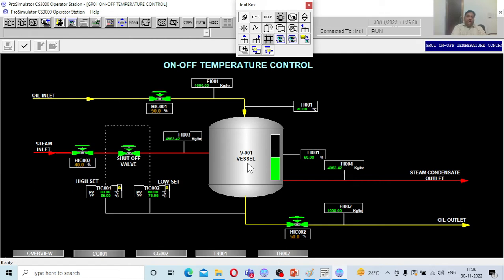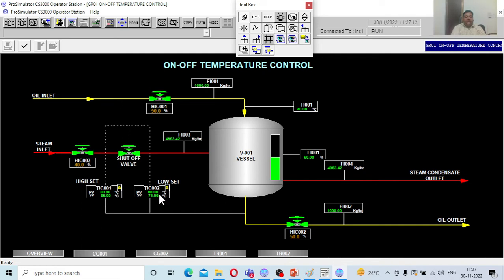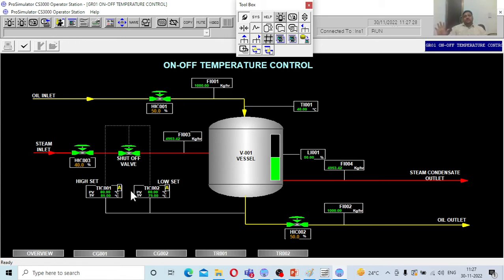The objective is to maintain the oil temperature in the vessel between 75 and 85 degrees. The sensor detects the temperature at the outlet and sends a signal to the controller as the process value. The process value — the oil temperature — is currently around 80 degrees centigrade, which is between the set points of 75 and 85. Everything is currently at steady state.